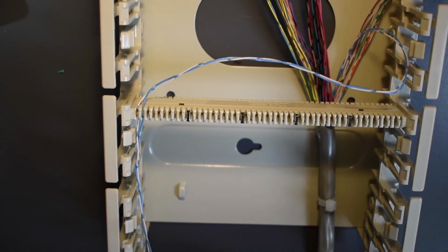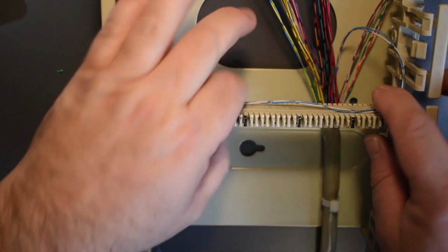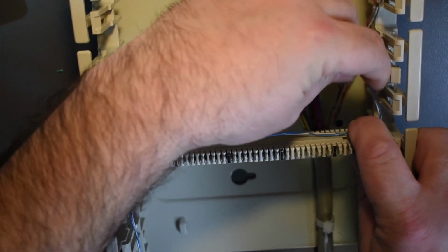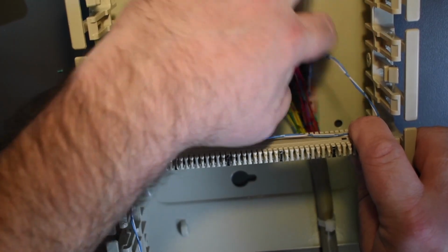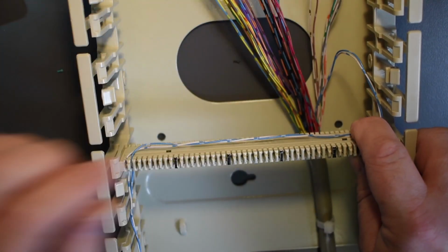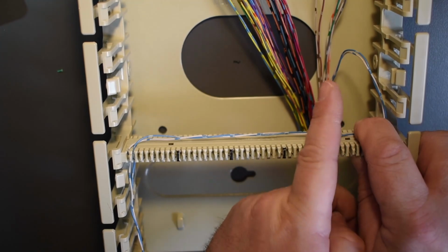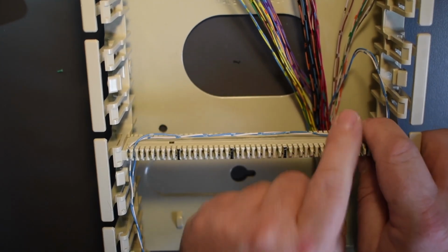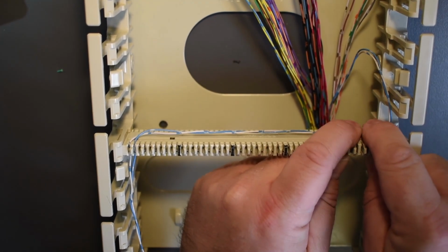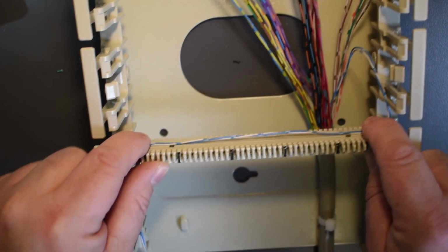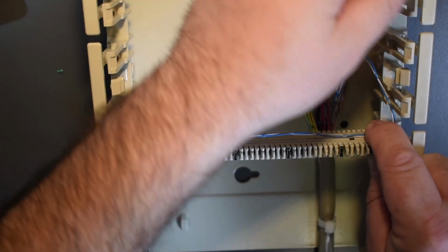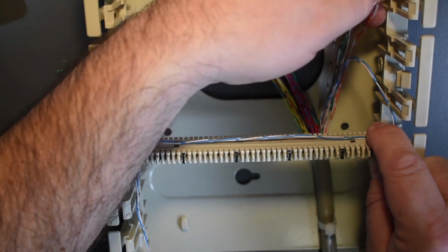Okay, so now what we have is a certain length of cable that goes along this termination strip, and we have a little bit of slack here. It is important to have that slack, and it is important that the cable goes around the slack, and it goes right here, and it starts running along the termination strip. It's extremely important. Do not do it like this. Don't ever do it. Please don't do it, because you're going to have to do it again.